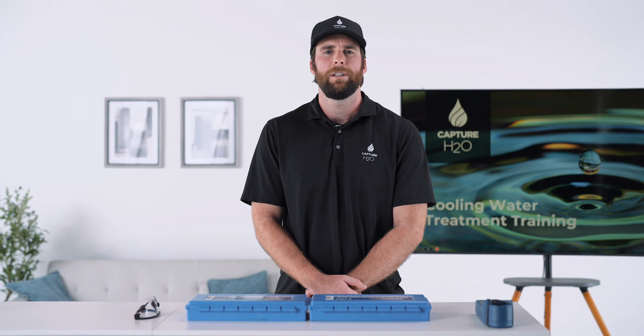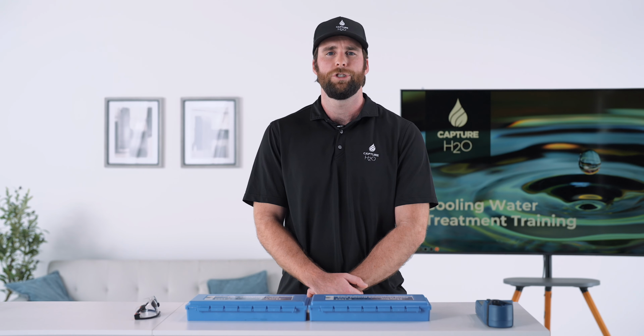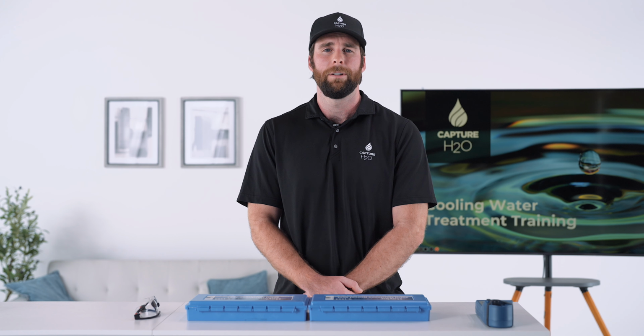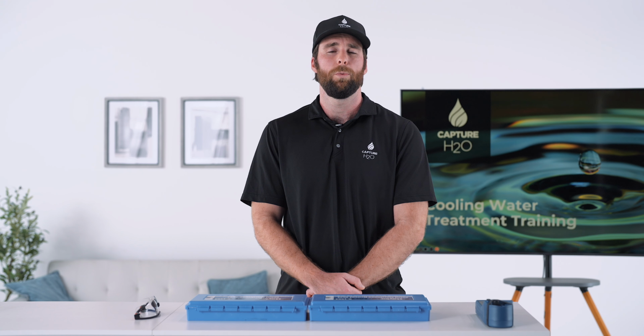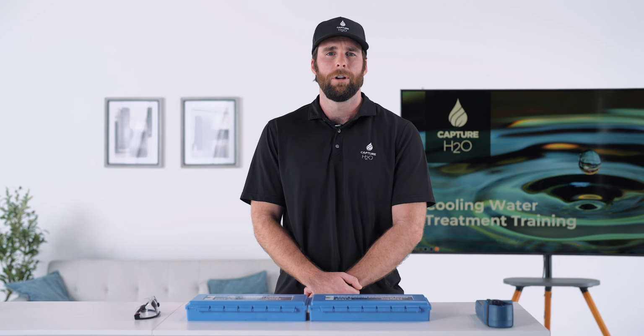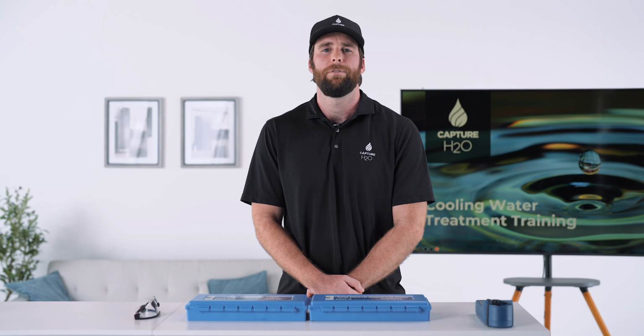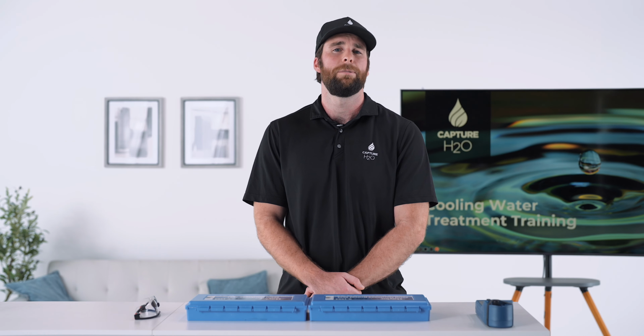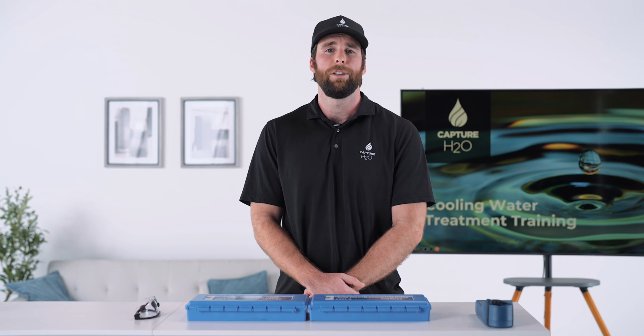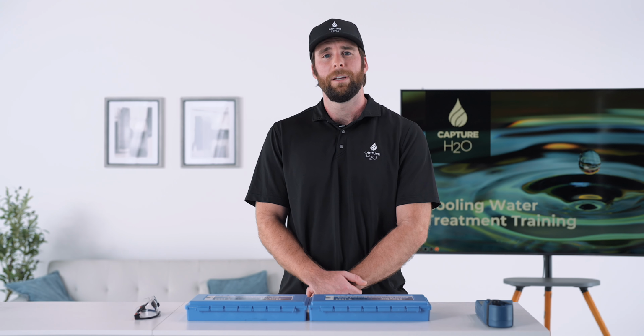You will be receiving snapshots of the reports generated by our inline probes connected to the controllers. It is important to monitor these to ensure that what we are seeing is both accurate and that we are responding to them quickly. If the tower, again, is losing water, you are not only wasting water, but leaving yourself susceptible to microbiome and excessive corrosion. If the softeners are not regenerating, hardness is being sent to the towers, meaning that you are potentially scaling your system, increasing your energy costs to complete that heat transfer.